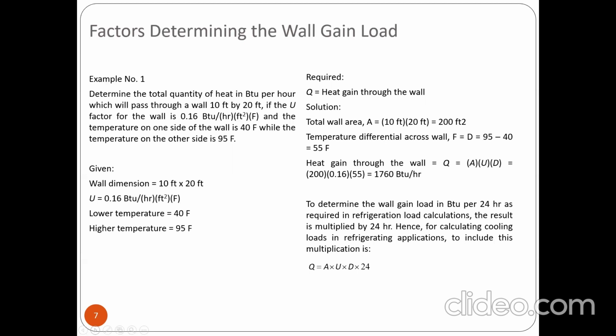To determine the wall gain load in BTU per 24 hours, as required in refrigeration load calculation, the result is multiplied by 24 hours. Hence, for calculating cooling loads in refrigerating applications, we include this multiplication: Q is equal to A U D times 24. A times U times D times 24.